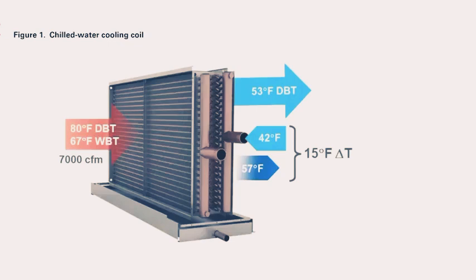Let us assume the entering air conditions are 80 degrees Fahrenheit dry bulb and 67 degrees Fahrenheit wet bulb, which equates to a 60 degrees Fahrenheit dew point. The air leaving the coil should be cooled to a temperature less than the dew point in order for the water vapor to condense on the coil surface and therefore remove the latent heat from the air. In our case, it is being cooled to 53 degrees Fahrenheit, which means that water vapor will be condensing out of the air to reduce its humidity.